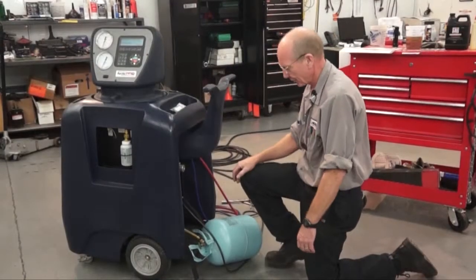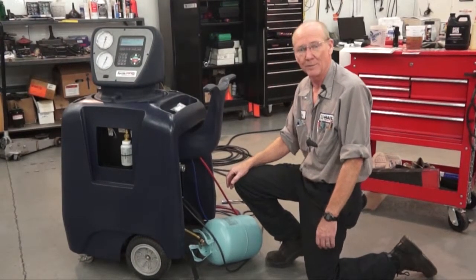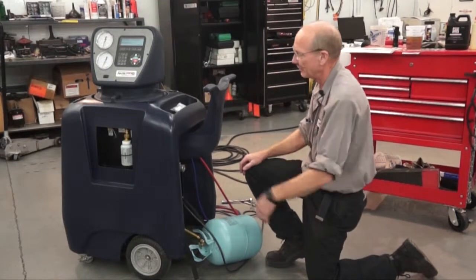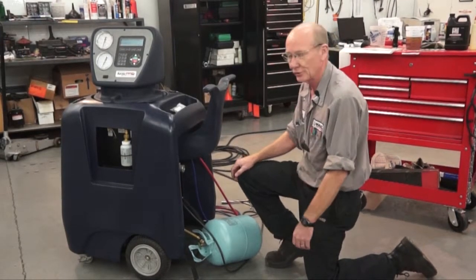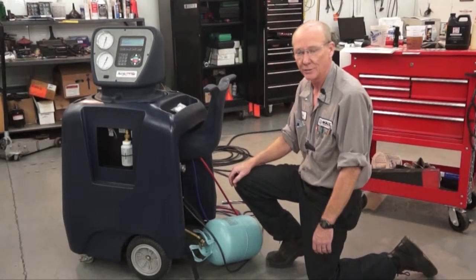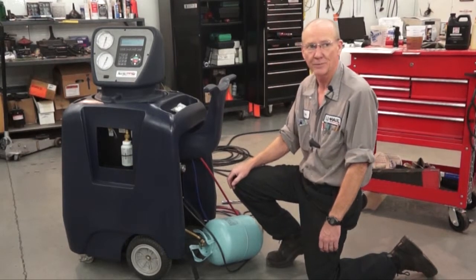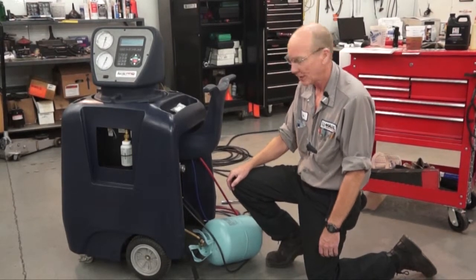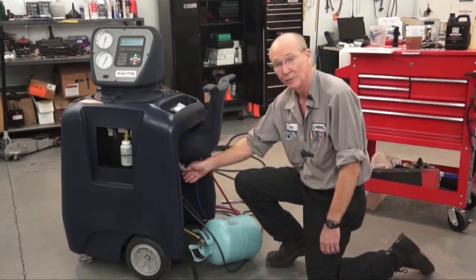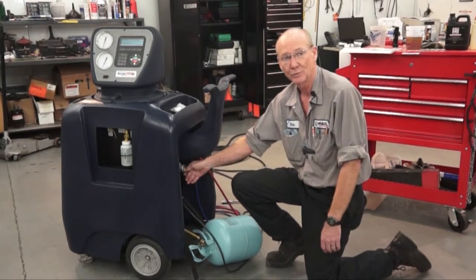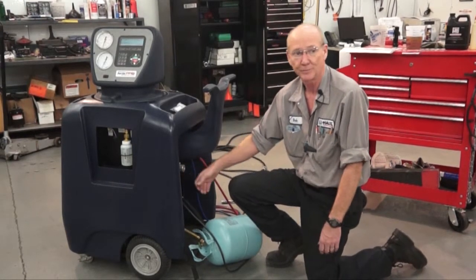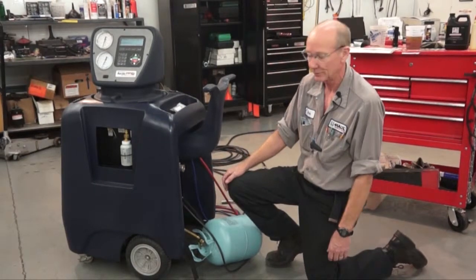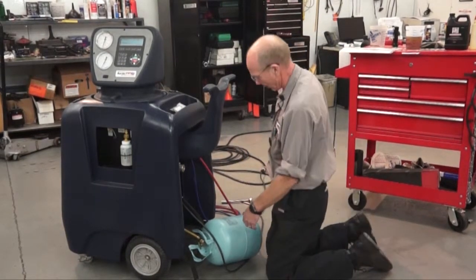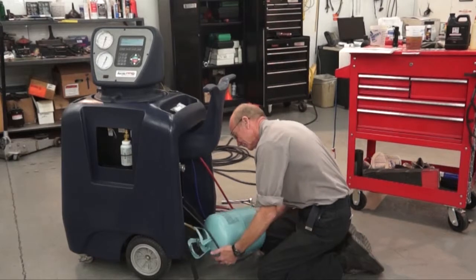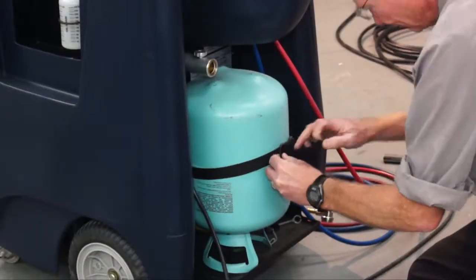Now that the filters are changed and I have new vacuum pump oil, and I reset my oil change to yes to change the oil, it'll run another 10 hours before it gives me another notification. Or if you happen to see this oil get a little cloudy, again, moisture will cause that, you may have to change it before the 10 hours is up. That's up to you. So I'm going to reinstall the tank, secure it.